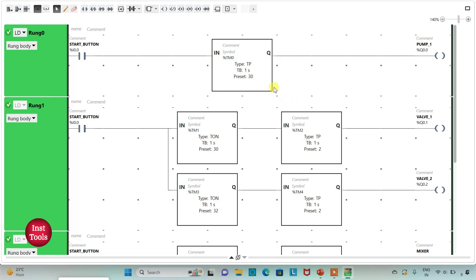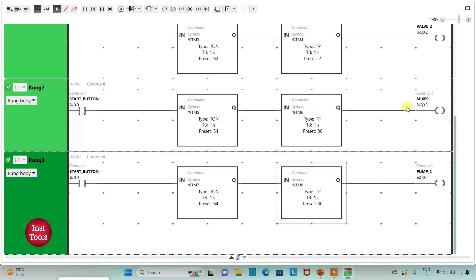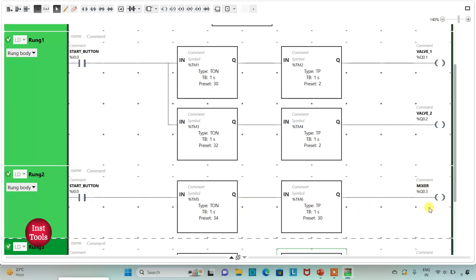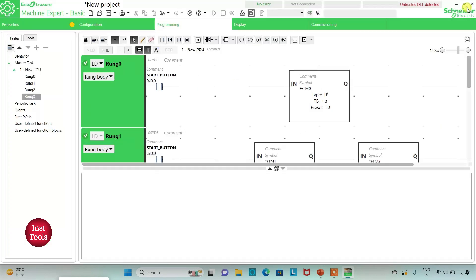So when the start button is turned on: Pump 1 turns on for 30 seconds; Valve 1 waits 30 seconds then turns on for 2 seconds; Valve 2 waits 32 seconds then turns on for 2 seconds; the mixer waits 34 seconds then turns on for 30 seconds; and Pump 2 waits 64 seconds — during which Pump 1, Valve 1, Valve 2, and the mixer were all active — and then Pump 2 turns on for 30 seconds, after which it stops. I will now exit full screen mode and compile the program.